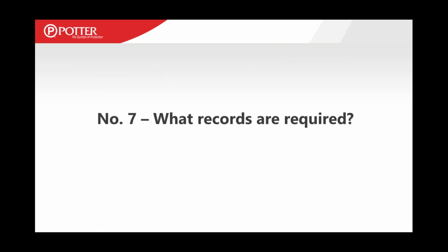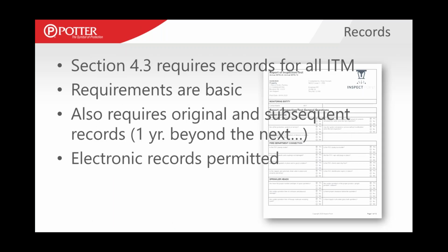So what records are required to be kept? What does NFPA 25 tell us? Well, it's all contained in Chapter 4. 4.3 requires records be made and kept for all inspection, testing, and maintenance. Anything that's done, whether it's recording the temperature, the pressure on a gauge on a daily basis in some cases, or the temperature in a fire pump enclosure, for example, a fire pump room in the wintertime, that's a daily inspection. So that record has to be kept every day, all the way up to 5, 10, 20-year inspections or testing of sprinklers and things like that. Any inspection, test, and maintenance is not done until there's a record of it. So 4.3 establishes all that.